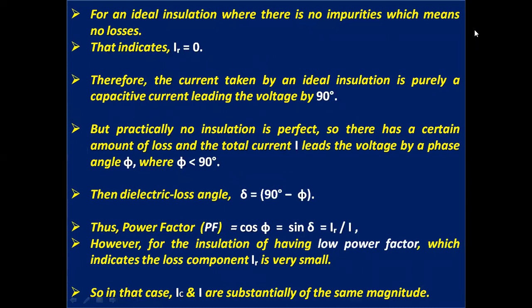For an ideal insulation where there are no impurities, which means no losses, IR equals 0. Therefore, the current taken by an ideal insulation is purely a capacitive current leading the voltage by 90 degree. But practically, no insulation is perfect. So there is a certain amount of loss, and the total current I leads the voltage by a phase angle phi, where phi will be less than 90 degree. Then dielectric loss angle delta equals 90 degree minus phi. Thus, power factor cos phi equals sin delta, that equals IR by I.